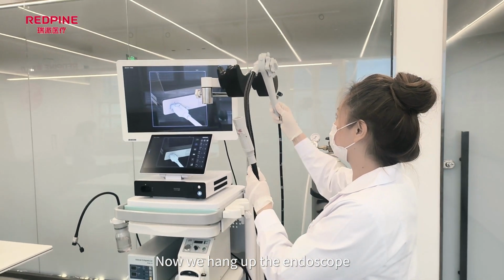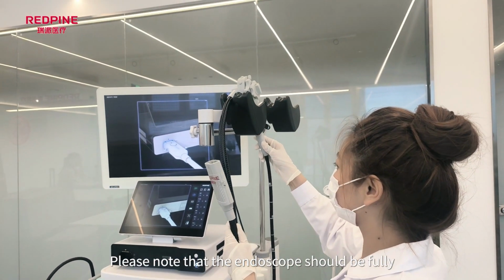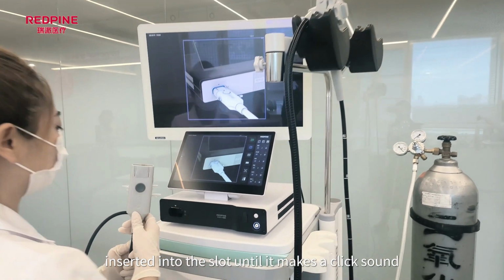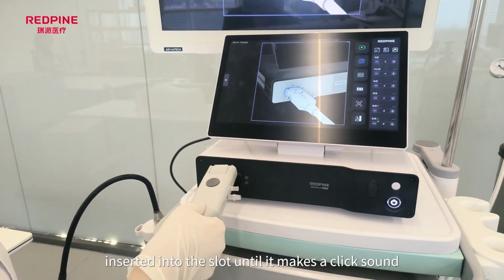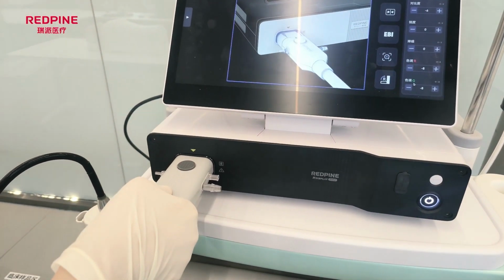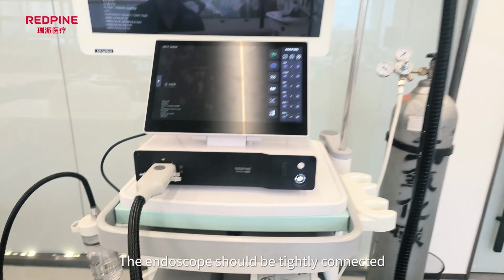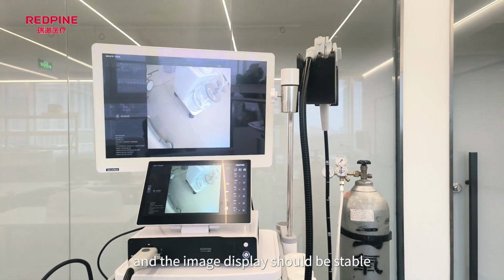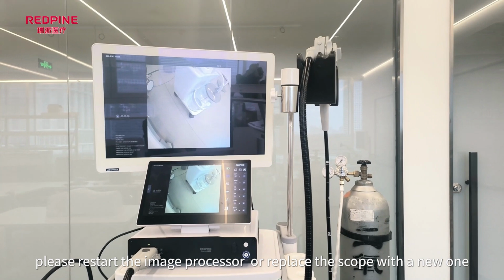Now we hang up the endoscope. Please note that the endoscope should be fully inserted into the slot until it makes a click sound. The endoscope should be tightly connected, and the image display should be stable. In the case of image lag, please replug the scope. If there is still lag, please restart the image processor or replace the scope with a new one.